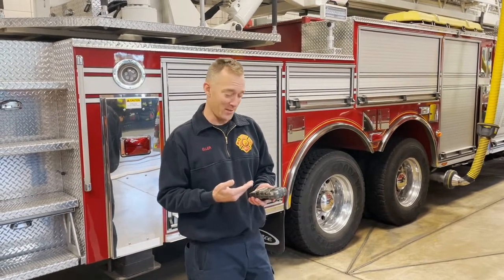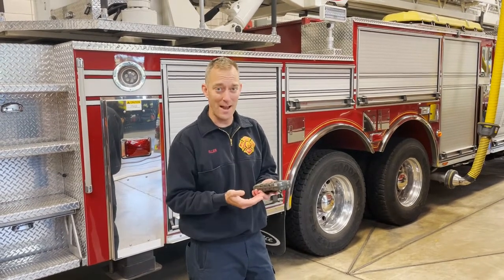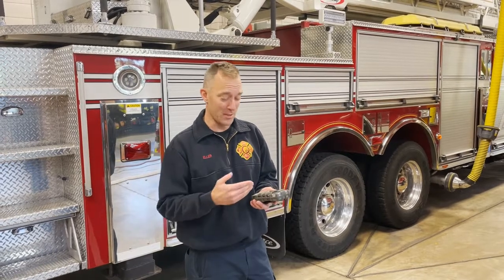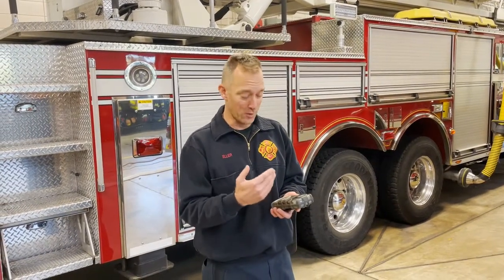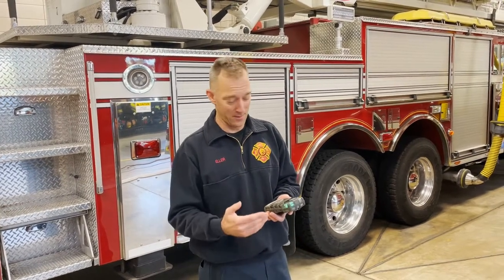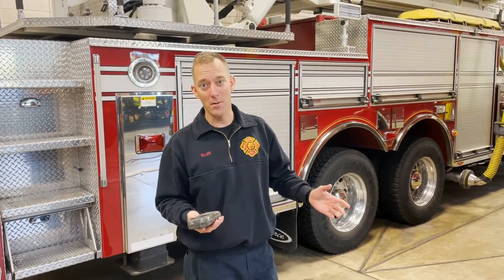When using this meter, give the sensors time to respond — the pump needs time to draw in the gas sample, and the chemical or electrical reactions inside take a little time. For the LEL sensor, wait a good ten seconds for an accurate reading. For the CO sensor, wait 15 seconds. Remember that both CO and methane, the primary component of natural gas, are lighter than air.